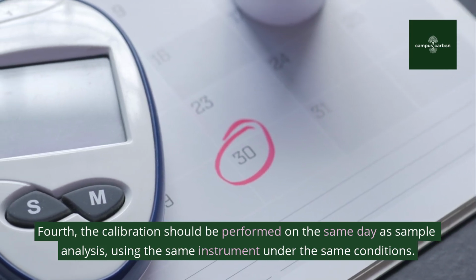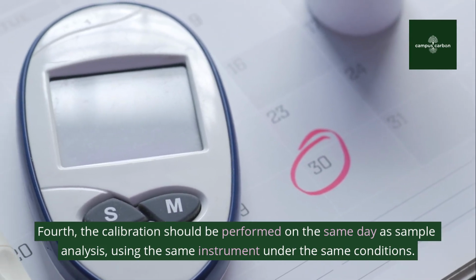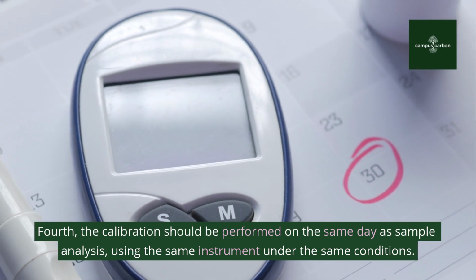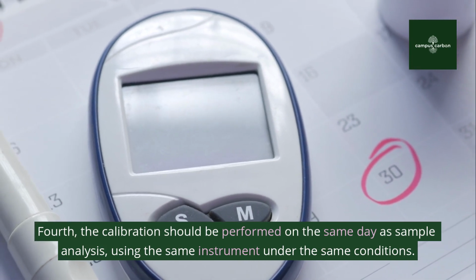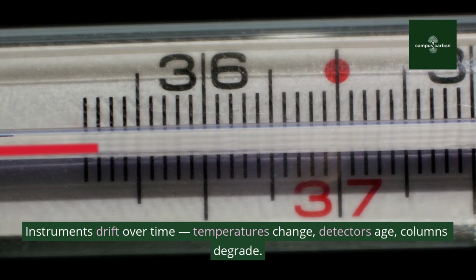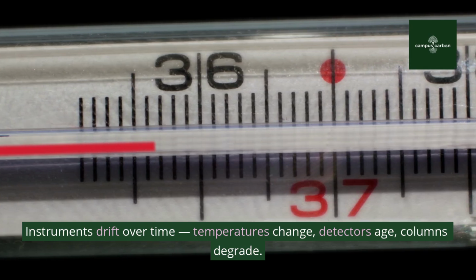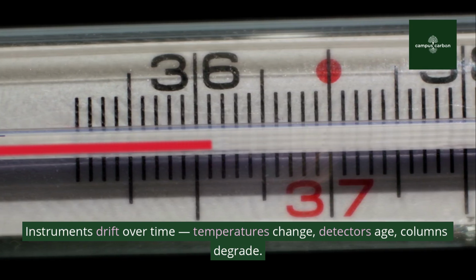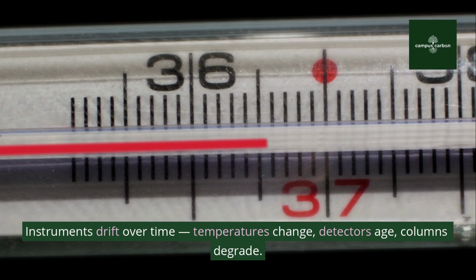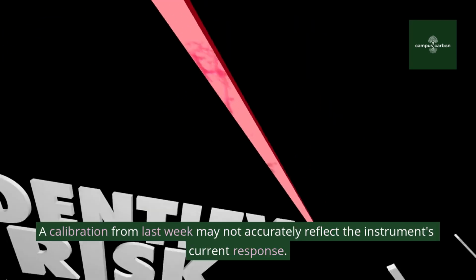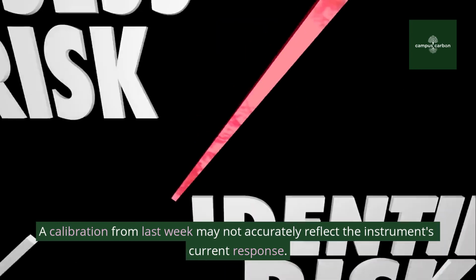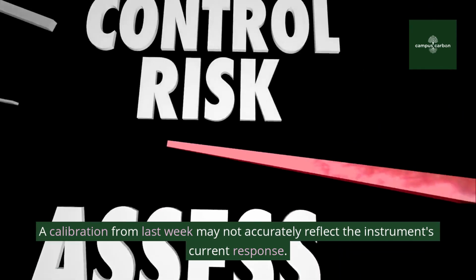Fourth, the calibration should be performed on the same day as sample analysis, using the same instrument under the same conditions. Instruments drift over time, temperatures change, detectors age, columns degrade. A calibration from last week may not accurately reflect the instrument's current response.